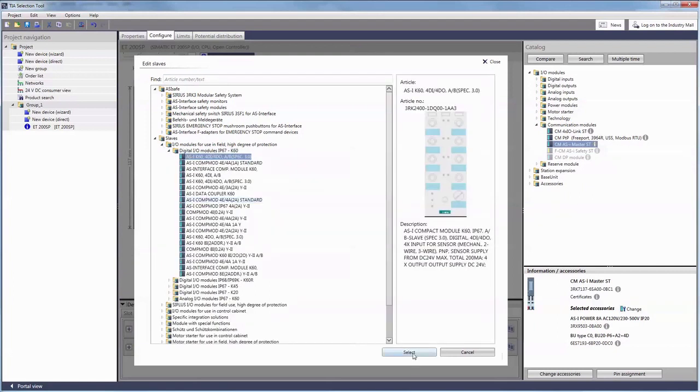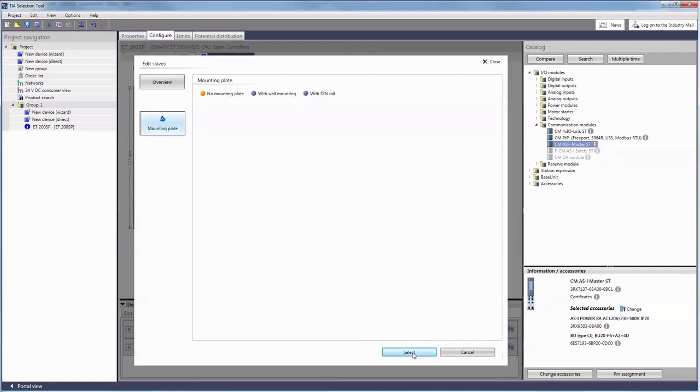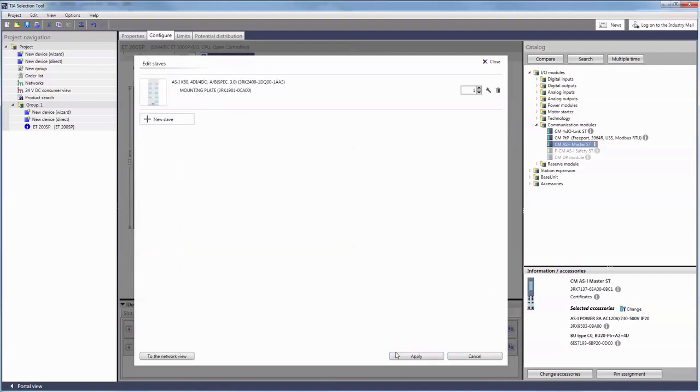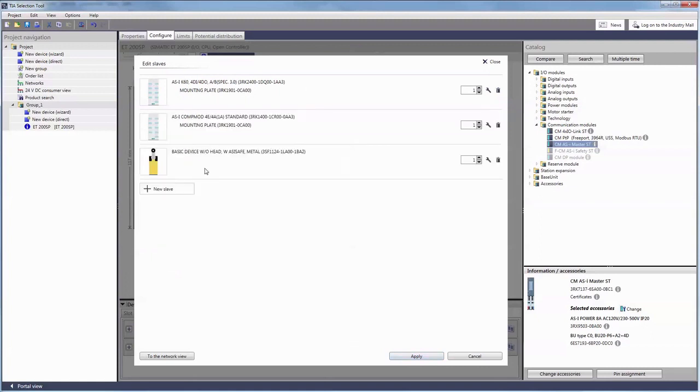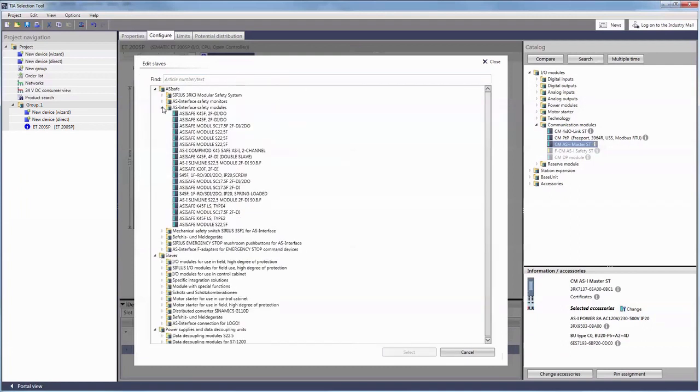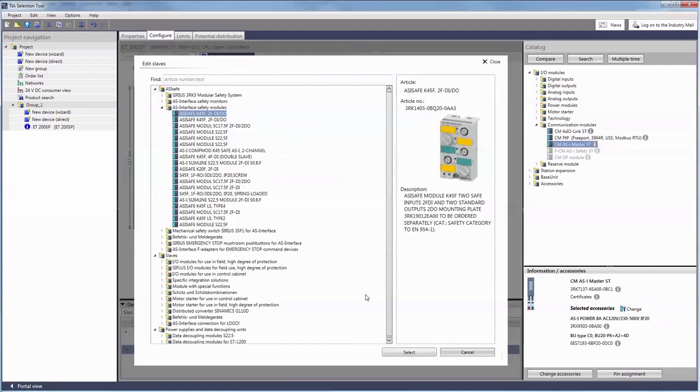Up to 62 slaves can be connected to the ASI master and are supplied with power over the ASI interface. The ASI interface also enables the direct integration of safety components.